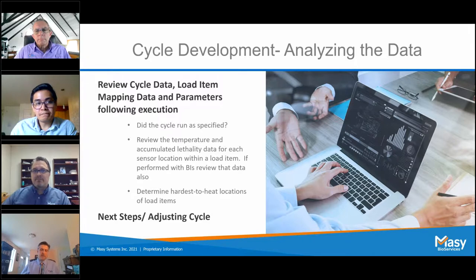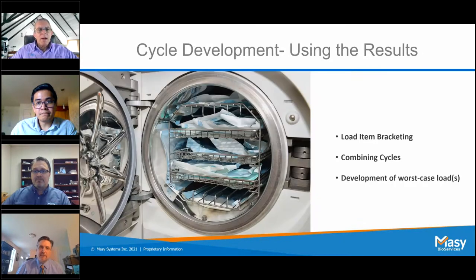Okay, great. So, John, using the results. By bracketing your load items and combining your like cycles, you'll have minimized your potential cycle count. Therefore, fewer cycles, less confusion, fewer errors. Every account always wants the minimum amount of cycles, because the last thing you want is to put the wrong load in, press the wrong button, have everything look good, and then have a failure. The other is that you can leverage the development results for the worst case loads for your future requalification programs or your continuous verification. We know this is the hardest-to-heat cycle, that's the one you want to requalify next year, or on a shorter cycle. Okay, so those are the recommendations for how to utilize the results.